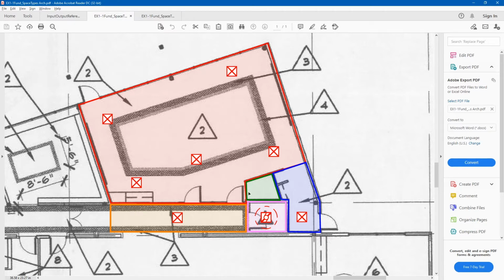The conference space and the storage area are basically open to each other, so it's not really important to separate this storage area out into its own thermal zone. So this is still defined as a storage space. It's going to calculate storage space lighting loads, storage space equipment loads, and people loads, but OpenStudio is going to combine it with the conference space. And like I said, we've got this entryway separated.